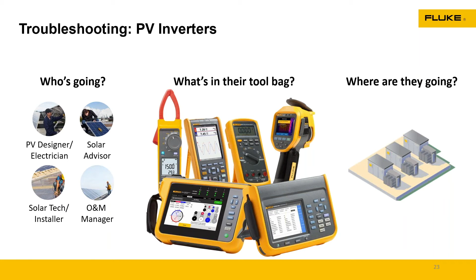So the inverters are super smart, but there's a lot of components in it. You've got DC capacitors, AC capacitors, you've got electronic boards, a tremendous amount of stuff going on. This is where we would want that plethora of tools. We want to be able to go in and check our voltage on our AC and our DC side. We want to make sure that if it's a three-phase type of system, that the loads are balanced correctly. Maybe there's something in the inverter causing something to be tripping, or you're overloaded on one side of it.